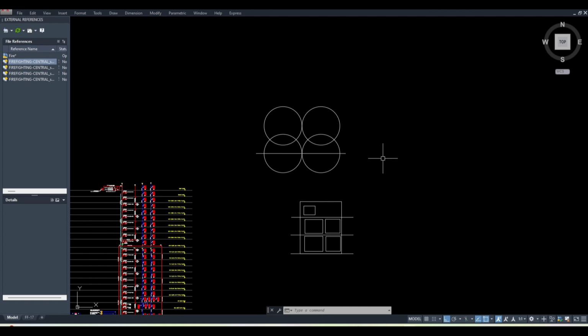Okay, and then the nearest: you cannot completely stack your sprinkler against the wall, but you have to have a distance of 100 mm. And then the maximum distance from the wall. Suppose there is an end wall and after that there is no sprinkler, that cannot be more than 1.8 meter away. So remember, are you guys writing all these things? Because you cannot remember it, it's a little bit tricky. The minimum distance from the wall to the sprinkler should be not less than 100 mm. Less than 100 you cannot go. How far can you keep it maximum? 1.8 meter. So you cannot go more than 1.8 meter away from the wall.